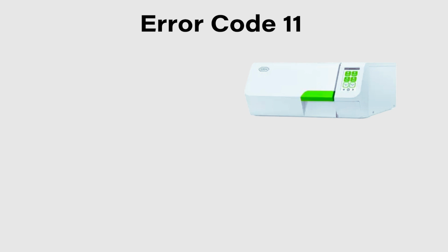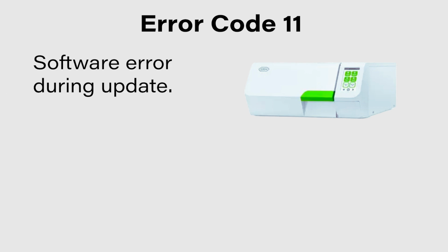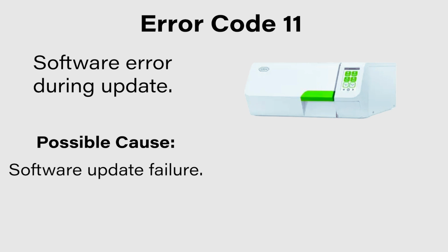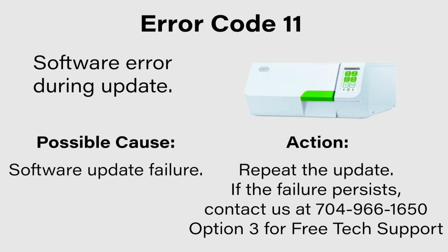If your W&H Lexa Mini is displaying an error code 11, that means that there was a software error during an update. The possible cause is a software update failure.